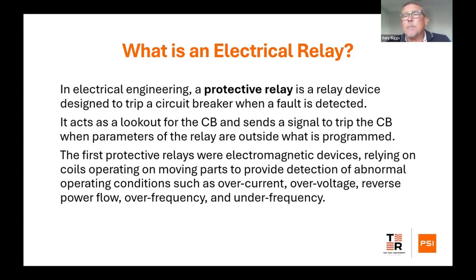So what it does is it monitors the circuit, and if it sees something untoward, and that can be anything that you've designed the relay to look for, it will tell the circuit breaker to operate and therefore protect the system. The first protective relays were electromagnetic devices relying on moving coils, operating on moving parts, and they provided detection of abnormal operating conditions such as overcurrent, overvoltage, reverse power flow, over frequency, under frequency. But in modern times, many modern relays will look at an awful lot more than that.